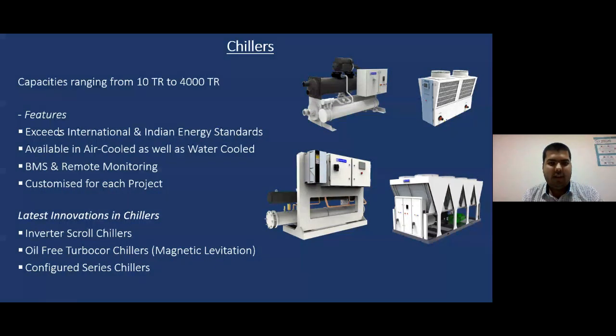So for example, if I have a requirement of 120 tons and there are standard models of 100 tons and 140 tons, a person has to buy 140 tons when there is no requirement for that. A chiller can be designed to suit an application of 120 tons only, as per the customer's requirement.